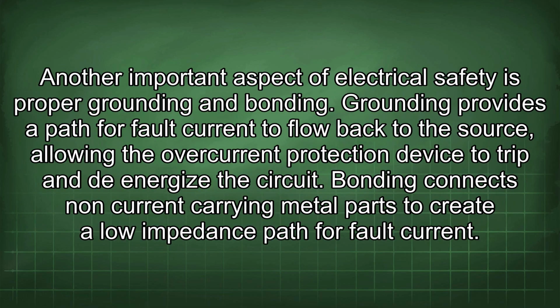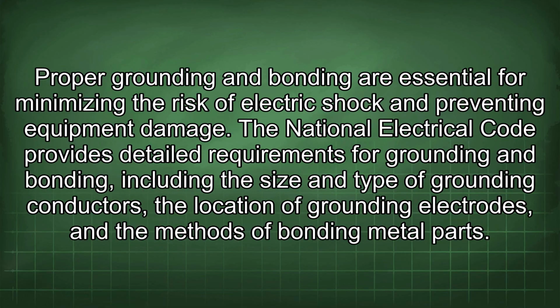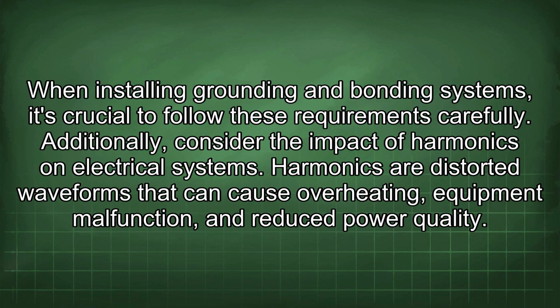Another important aspect of electrical safety is proper grounding and bonding. Grounding provides a path for fault current to flow back to the source, allowing the overcurrent protection device to trip and de-energize the circuit. Bonding connects non-current carrying metal parts to create a low impedance path for fault current. Proper grounding and bonding are essential for minimizing the risk of electric shock and preventing equipment damage. The National Electrical Code provides detailed requirements for grounding and bonding, including the size and type of grounding conductors, the location of grounding electrodes, and the methods of bonding metal parts. When installing grounding and bonding systems, it's crucial to follow these requirements carefully.